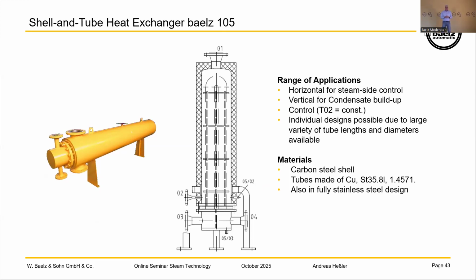Now I get it from the side, copper in English. Normal steel or stainless steel. We normally use tubes with stainless steel as a standard. That's for all our heat exchangers, because it's the best solution with regard to costs and heat exchanging. We can also build this in a fully stainless steel design. The tubes are from 10 to 12 and a little bit bigger, with different kinds of wall thickness.